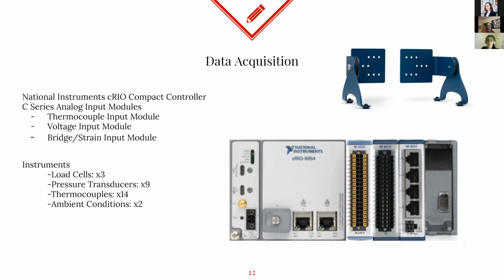We're going to be getting analog input modules for the thermocouples, the voltage, and the bridge and strain. The thermocouples will go into the thermocouple input, the ambient conditions and pressure transducers will be connected to the voltage input, and the load cells will be connected to the bridge strain input. That's on the blue device, showing how it'll be attached to the panel.